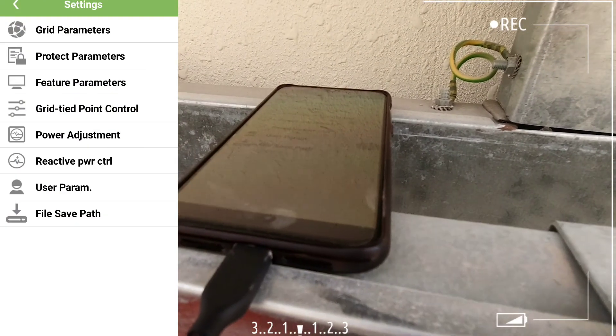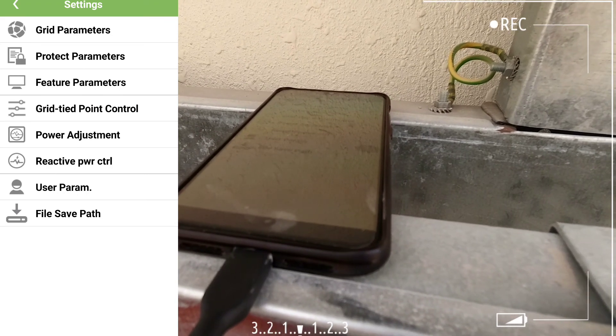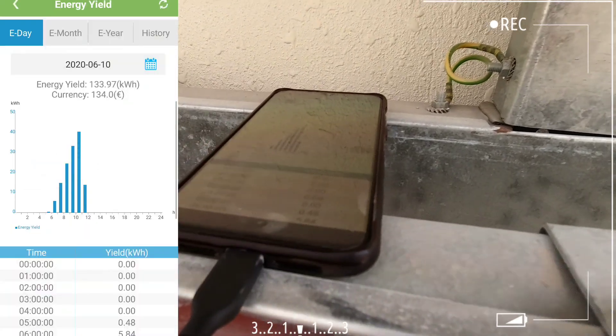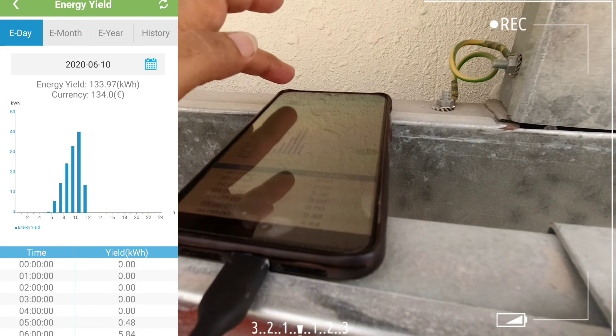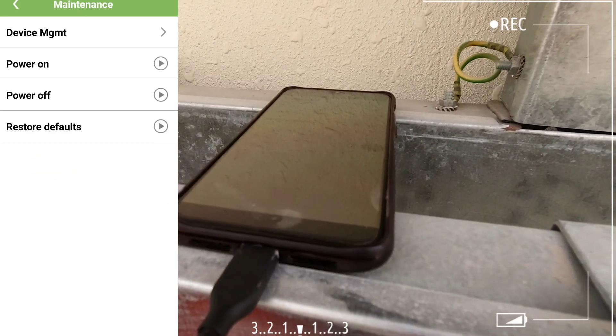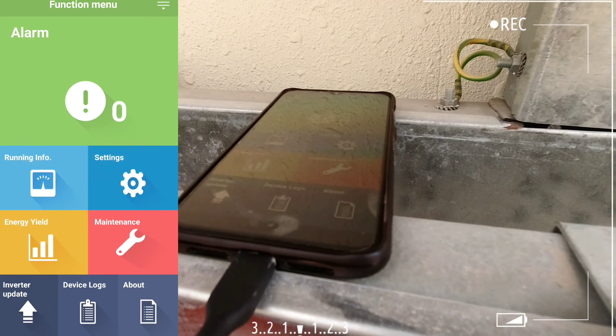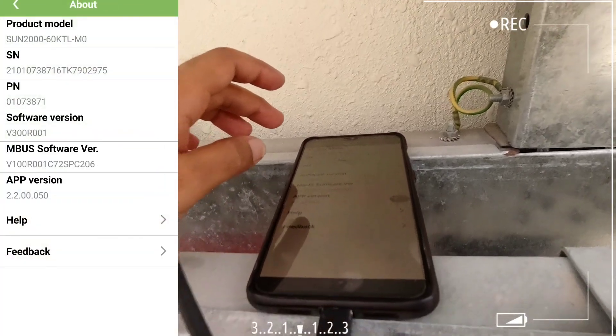Going to settings, you can control grid parameters, protective parameters, feature settings, grid tie, power adjustment, and user parameters. There is also a separate energy yield section where you can view yearly, monthly, and daily energy yield. Under maintenance, you have device management, power on/off, and restore default settings — all of which can be changed from this app.